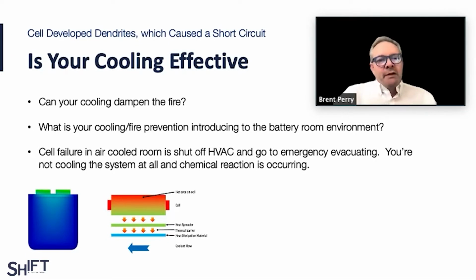Today there are effectively air-cooled systems, semi-air-cooled or semi-liquid cooled systems, and liquid cooling systems. The challenge with air cooling is simply managing to maintain the temperature of the cell at a level that helps manage a fire or explosion and simply prevent it. Air cooling requires about 3,200 times more air than liquid in order to manage temperature.